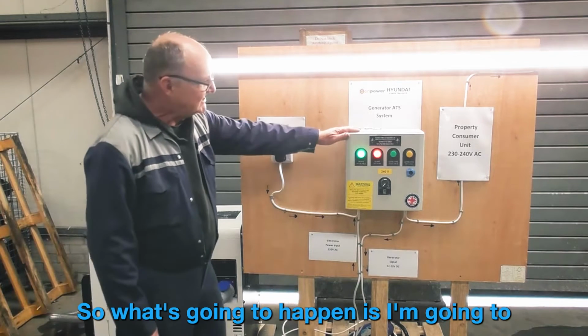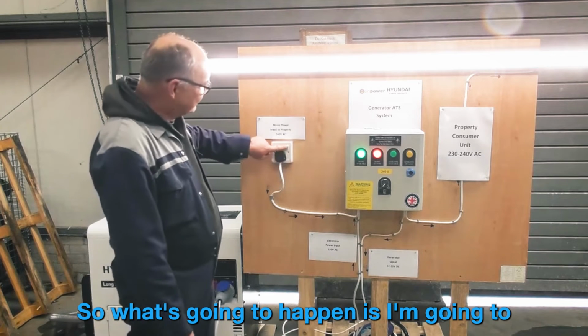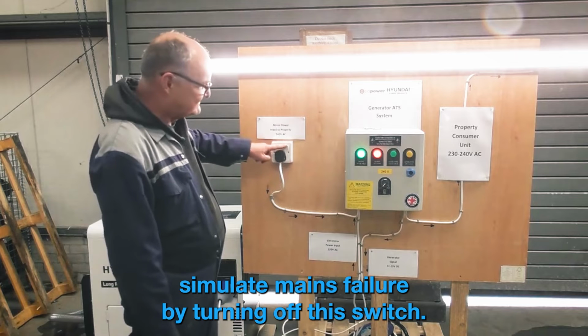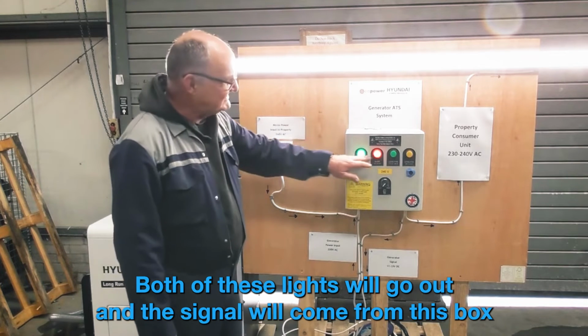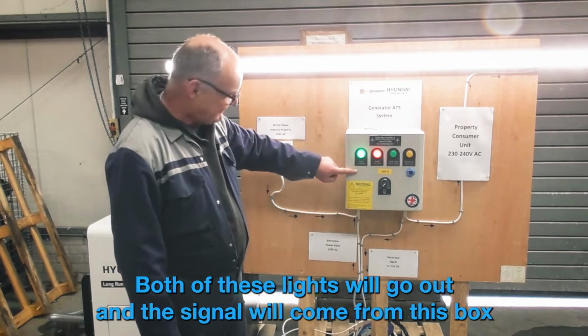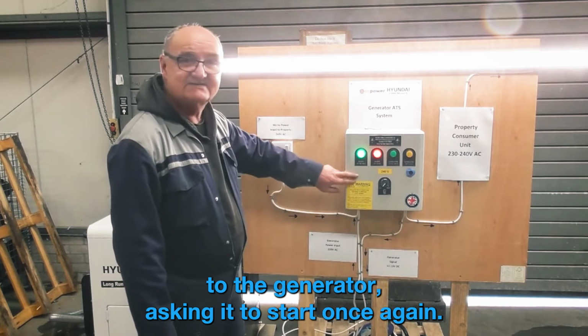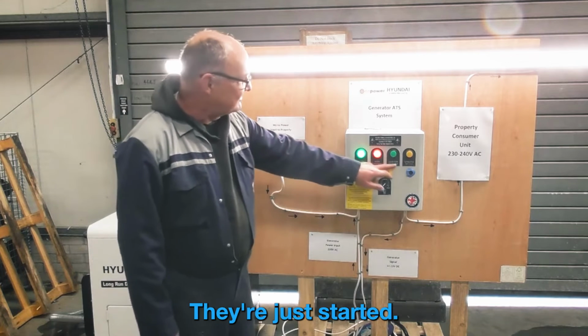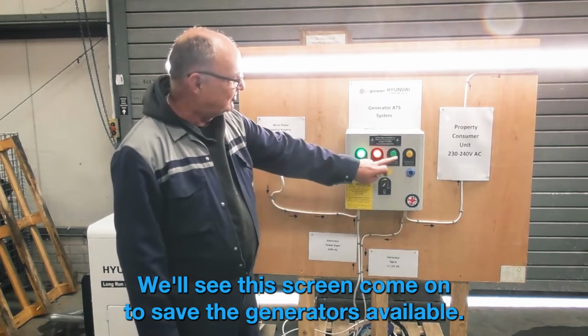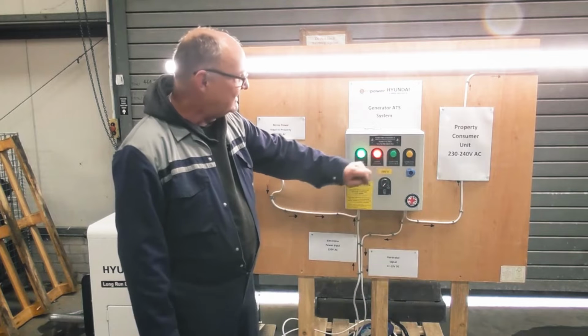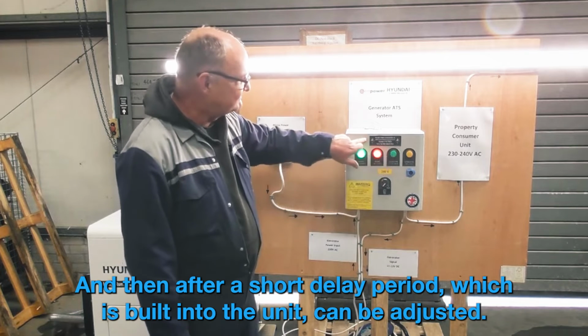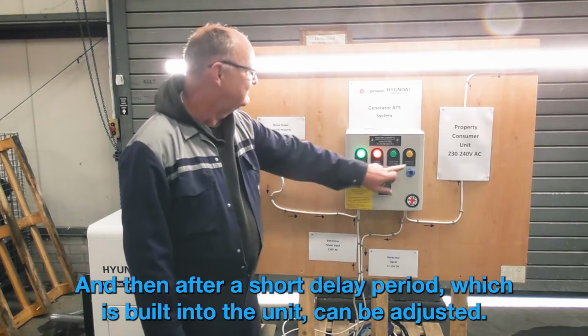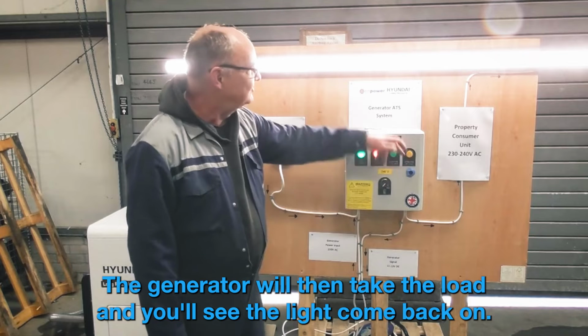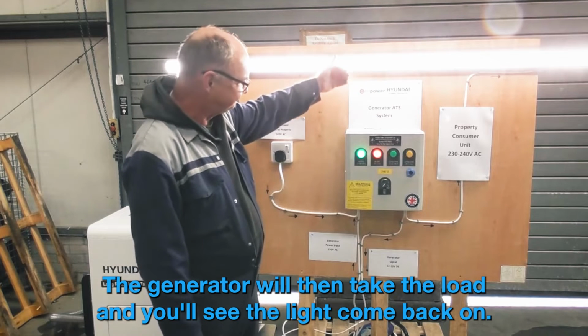What's going to happen is I'm going to simulate mains failure by turning off this switch. Both of these lights will go out, and a signal will come from this box to the generator asking it to start. Once the generator has started, we'll see this green light come on to say the generator is available. After a short delay period, which is built into the unit and can be adjusted, the generator will take the load and you'll see the light come back on.